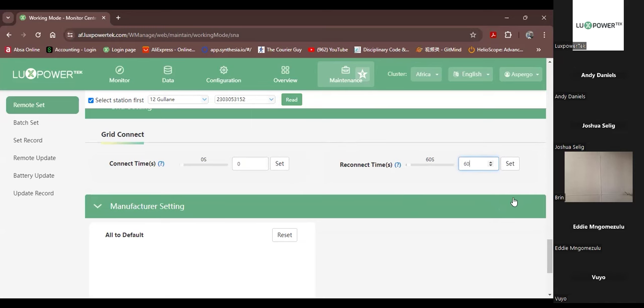And then when the grid goes and there's load shedding and the inverter goes to the off-grid mode, then it obviously supplies the PV and battery to the load. And when the grid comes on again, this will be your delay. Here I can set a 60-second delay. I can even set a 300-second delay, which is 5 minutes.